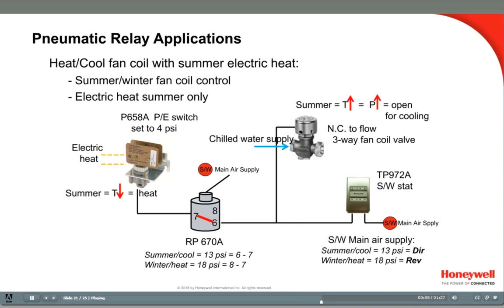In the summer, the main air supply is at 13 psi. This puts the thermostat in the cooling mode — it's direct-acting and the valve modulates to cool the rooms. The RP670 summer-winter relay now connects port 6 to 7, so the branch air passes to the P658A P/E switch. If the room cools down, the electric heat panel can now provide warmth. No heat is possible from the coil because it's full of chilled water all summer.